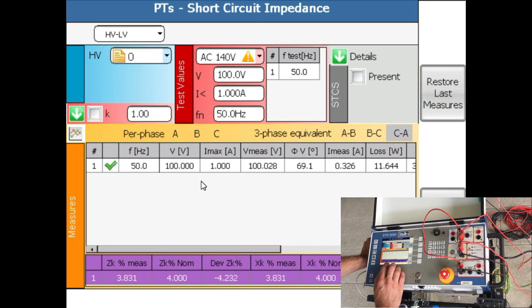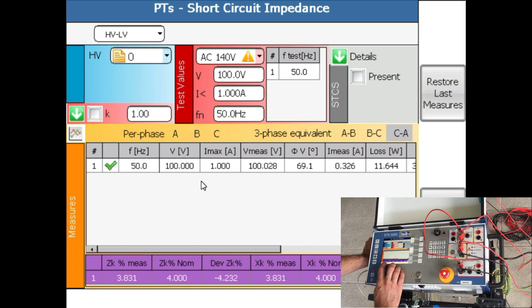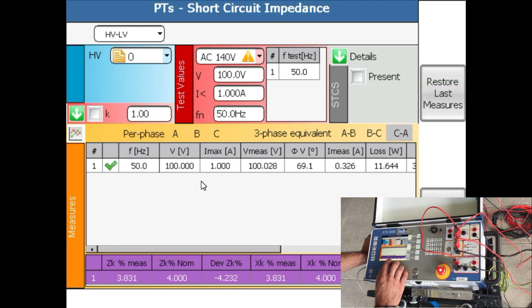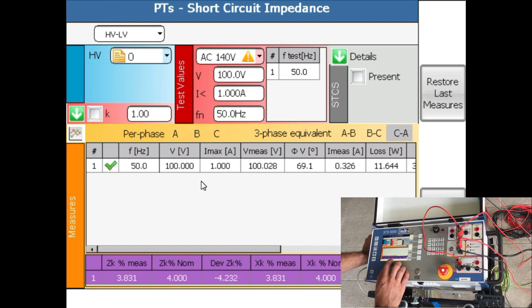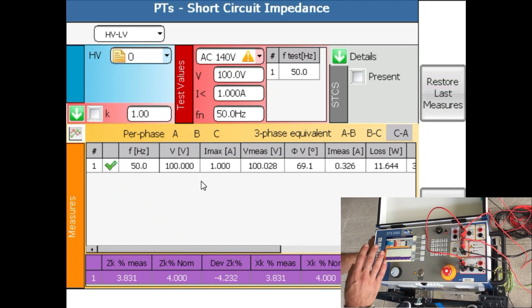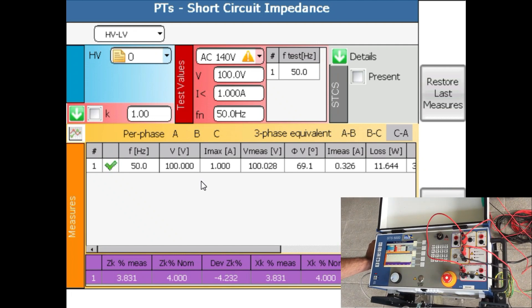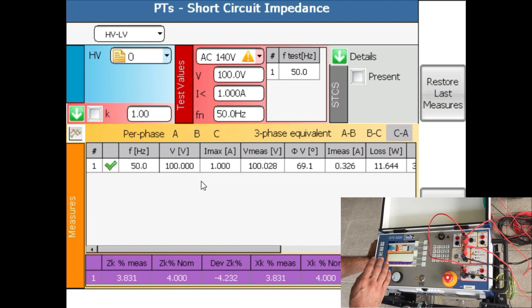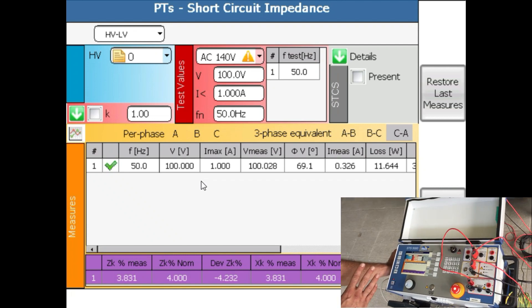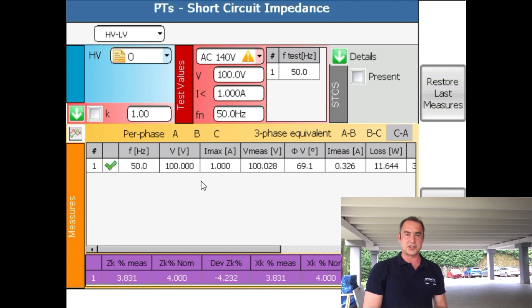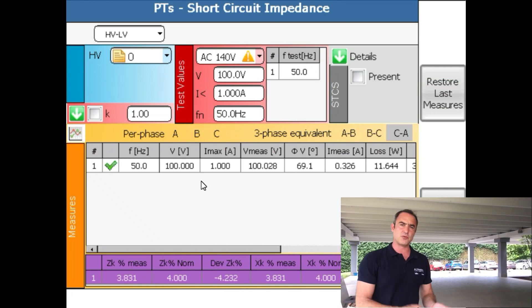The nominal value is 4%. We got 3.83. There is a deviation of 4.23%. For me in this case for this transformer this is a good result. What is a good or bad result definitely depends from a standard in a certain country for a big and for a small transformer.